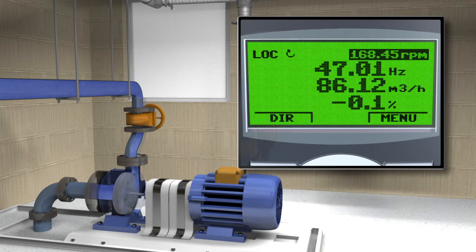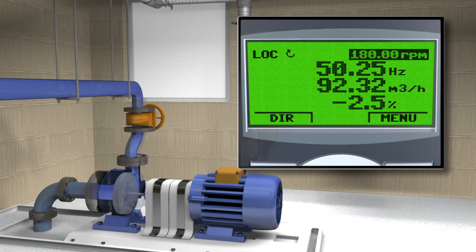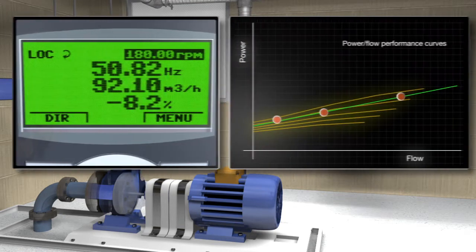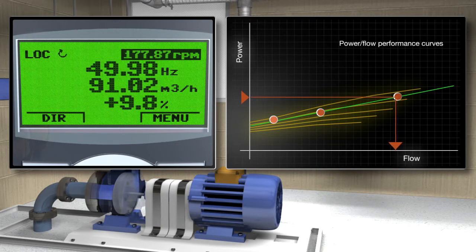Flow calculation is either sensorless or measurement data for the calculation can be supplied using pressure transmitters. The user can either define a power flow or head flow performance curve as the basis for the calculation.